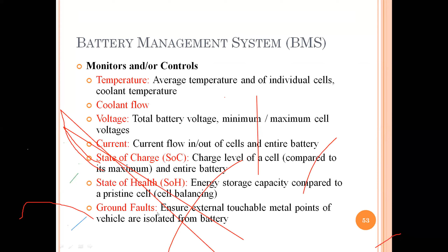The first one is current monitoring. Second is SOC monitoring, where you can monitor the highest and lowest value of SOC. Then voltage monitoring, where you can monitor the whole voltage, high cell voltage and low cell voltage. Then temperature monitoring, high temperature and low temperature. And there is discharge current limit set for the system, and charging current limit set for the system. So these are the battery management system parameters.